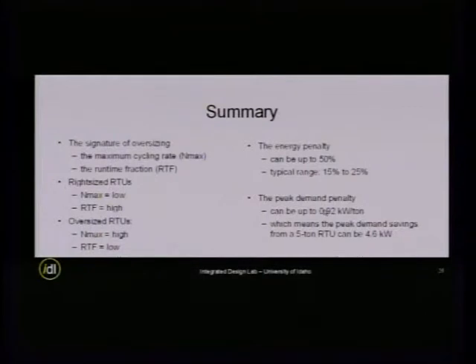This is considerably, first of all, this is considerably higher than what was found in the old California study. They found around 0.5, 0.6 kilowatt per ton. What we found here is not representative because they measured literally hundreds of units and we measured only 8. So there's not enough variation in our data. But what is important is the parameters.